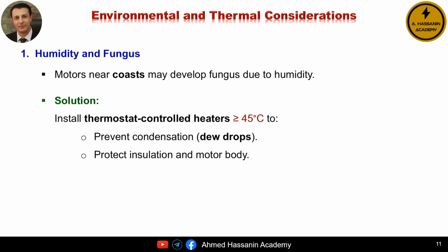Alright, let's switch gears and talk about environmental and thermal considerations. Basically, how the environment can affect motor operation. First up is humidity and fungus. Motors that operate near the coast or in very humid areas are especially vulnerable. The moisture in the air can cause fungus to grow on insulation or even on the motor body itself, which can lead to corrosion or damage over time.